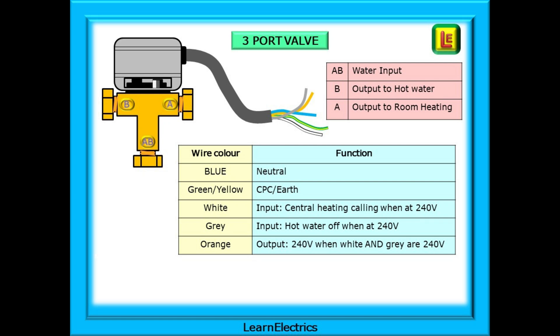The valve will normally come with a five wire lead attached to it. Blue is neutral, green and yellow is the earth or CPC wire. The white input wire will be at 240 volts when the central heating is calling for heat. It is important to understand the grey wire's function. When the grey wire is at 240 volts, this is telling the valve that hot water heating is not required. And more on this soon.